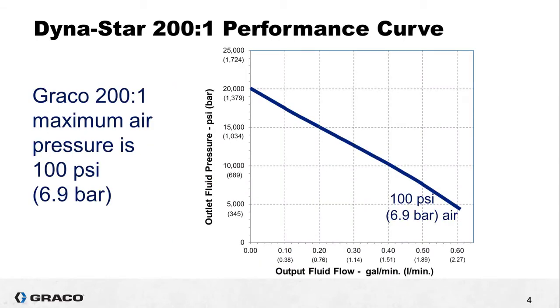So now at maximum air pressure we can see that at 20,000 psi there is no flow from the pump. That's called the stall pressure. Next let's find the mark that indicates 16,000 psi of outlet pressure and follow it to the right. When we draw a horizontal line over from this point it intersects our pump performance curve right here. Now when we draw a vertical line straight down from that point we see that the flow rate at 16,000 psi is just a hair over 0.16 gallons per minute because each of these ticks represents another 0.02 GPM.